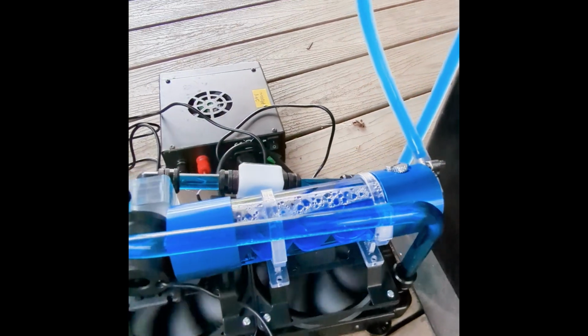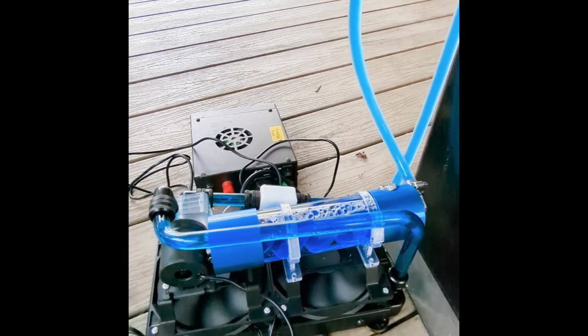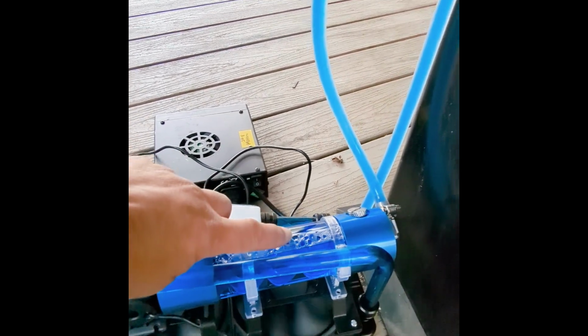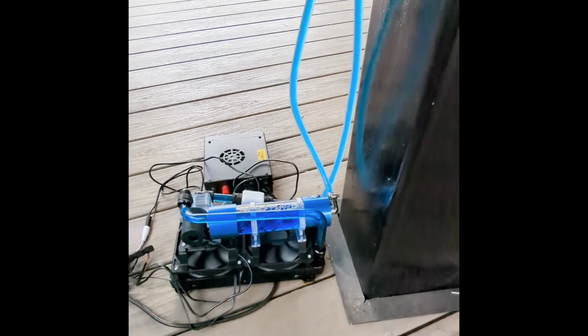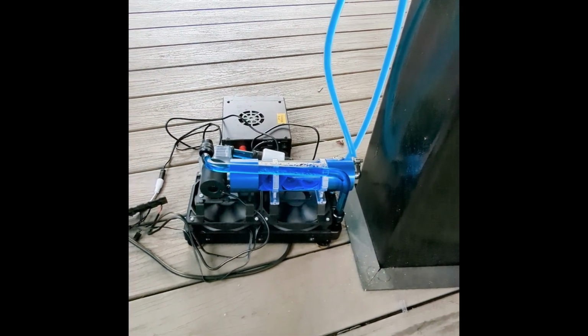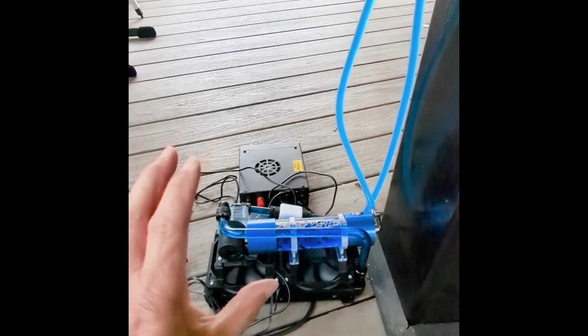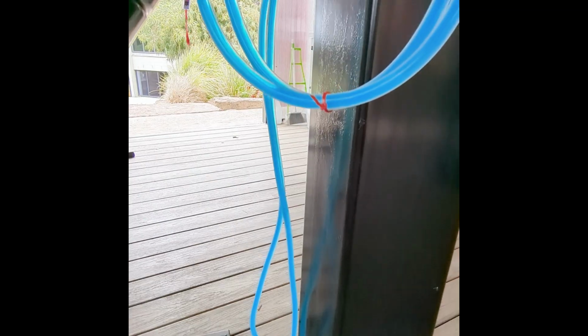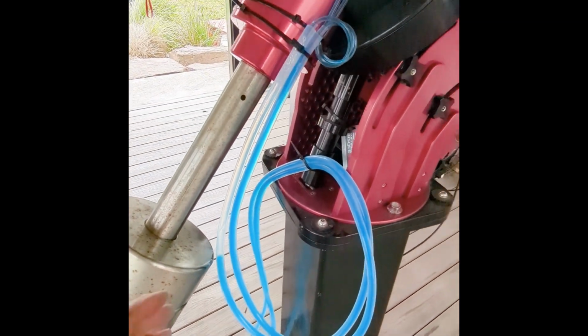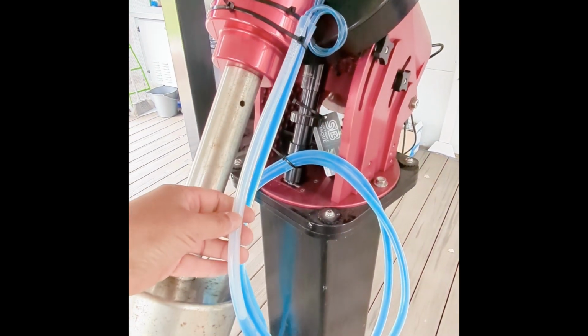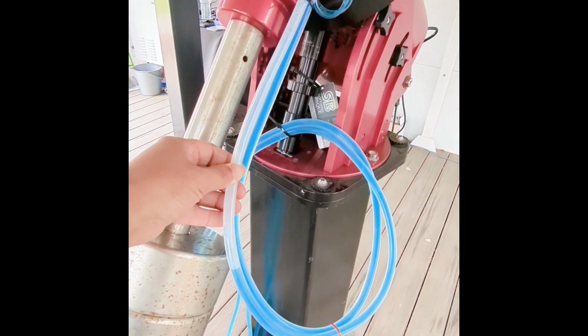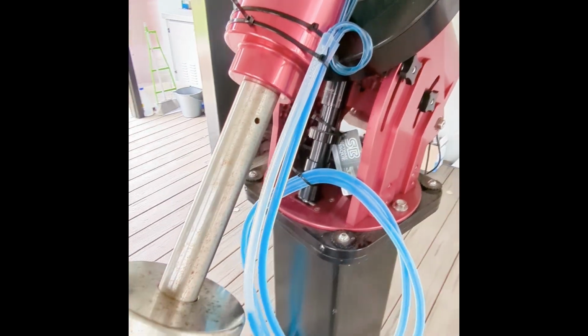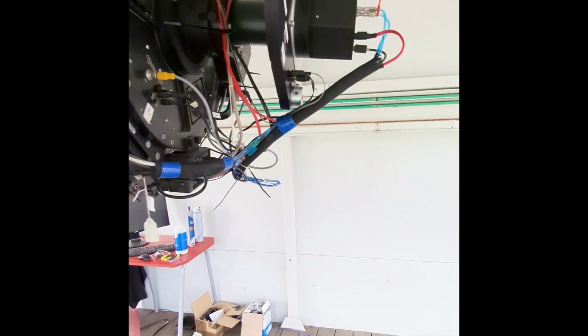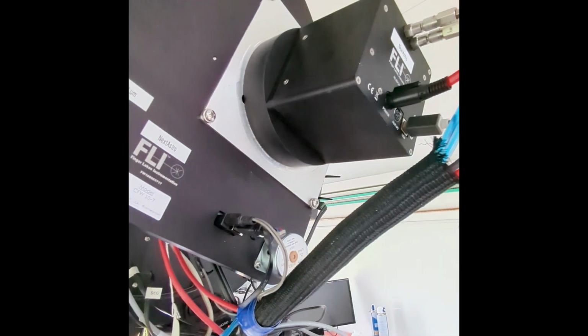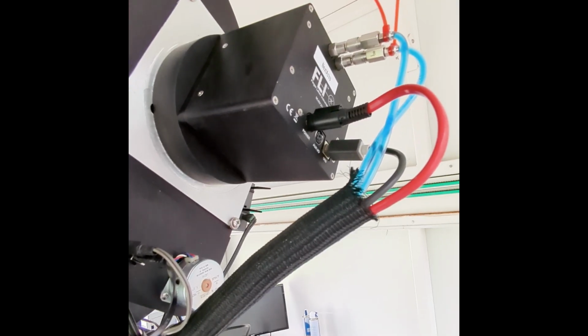We found that bleeding the system was quite laborious. This accumulator accumulates the air, but it did require turning the pump over and over, backwards and forwards, this way and that, until all the air was bled out. Even now, about 4 days after I did the installation, I see one of the tubes has a few mils of air accumulated, so I'll need to bleed that out as well. It turned out to be a lot more complicated a job, but that FLI imager is now running at -20 degrees - very successful, but not an easy job.